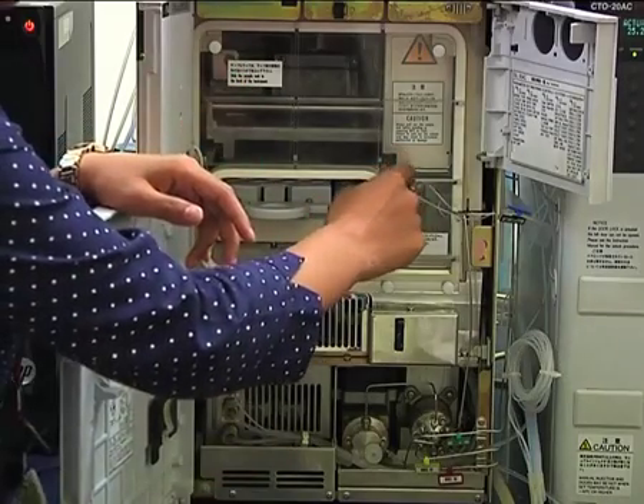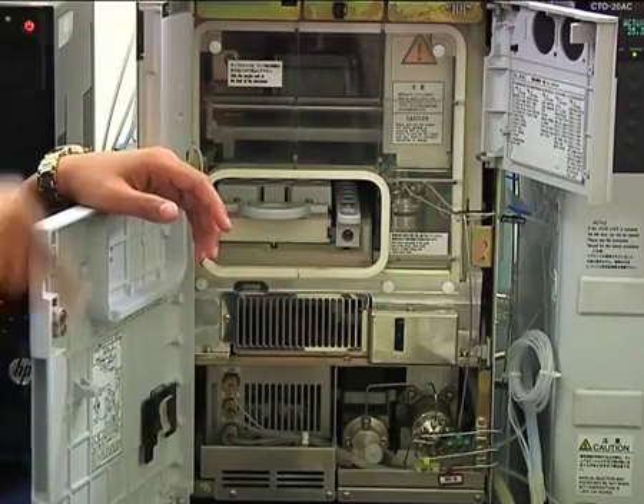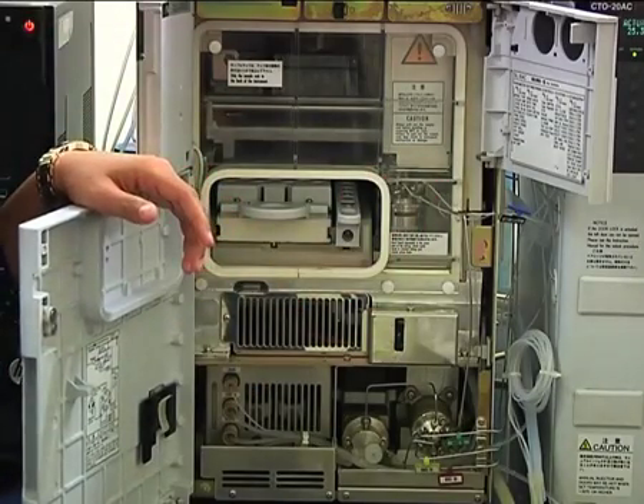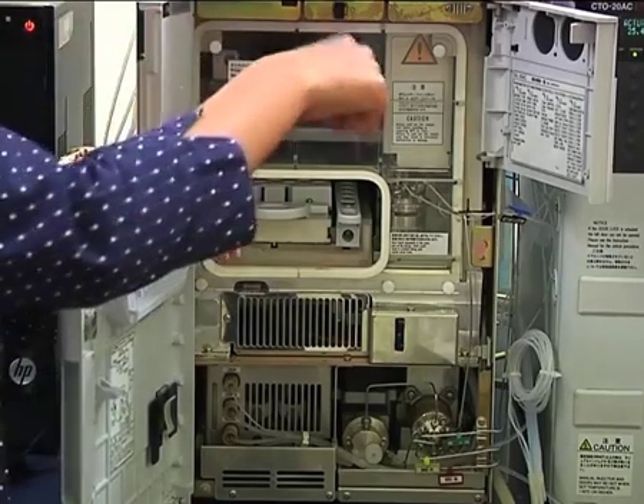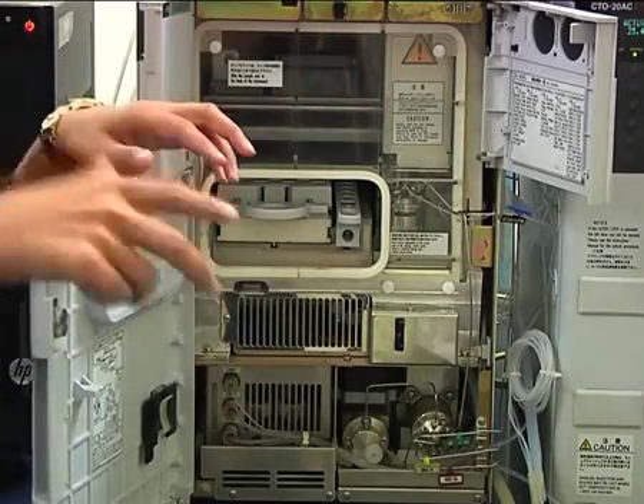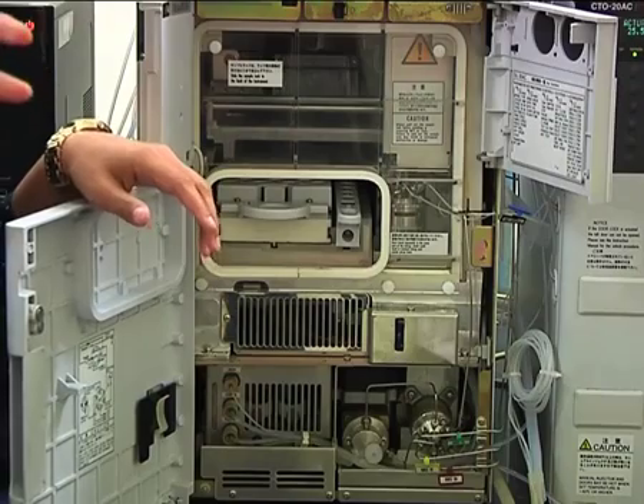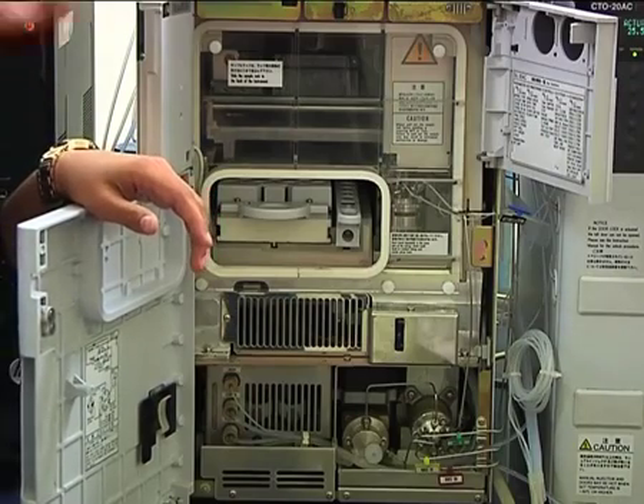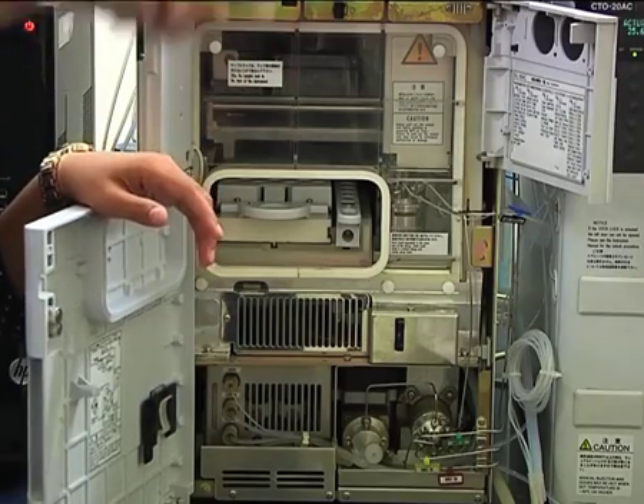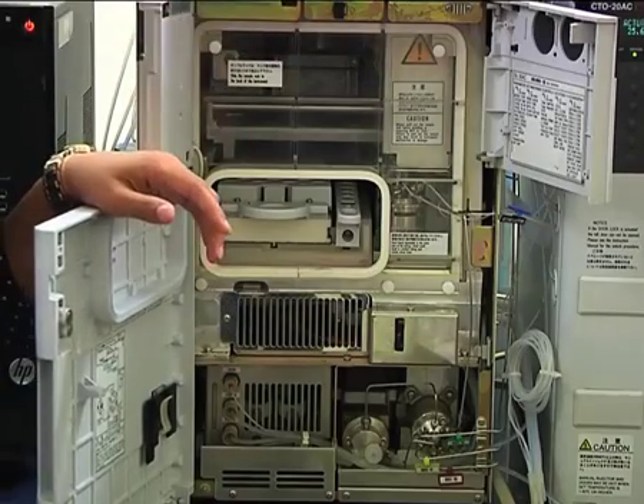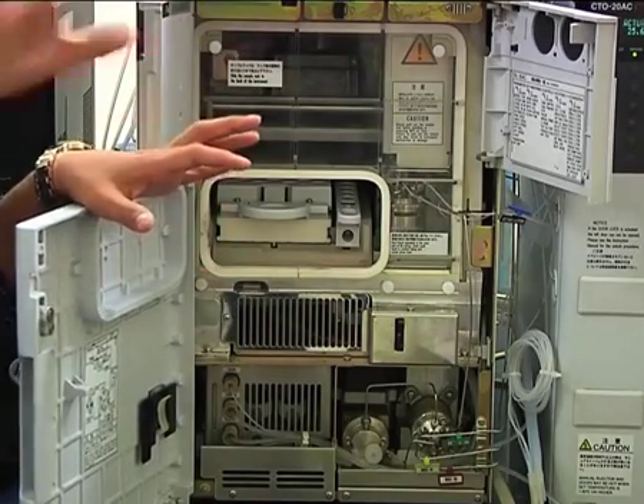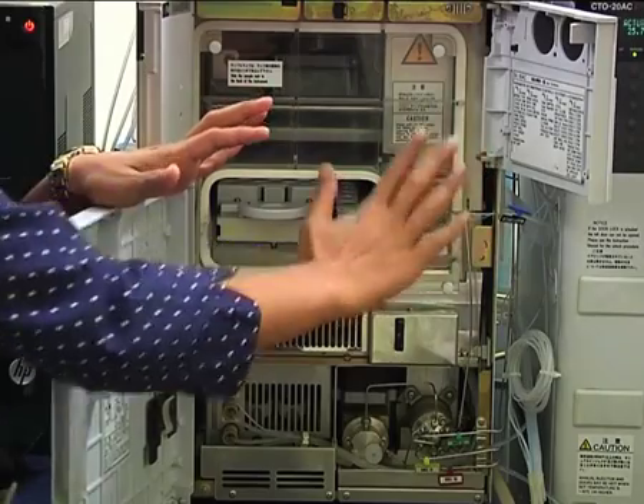Now the high pressure valve: your mobile phase will always pass through the high pressure valve, and there will be a sample loop attached to the high pressure valve. So whenever you do injection, the mobile phase will switch and flow through the sample loop, collect the sample, and then pass on to the column. So the mobile phase is always passing through this high pressure valve.